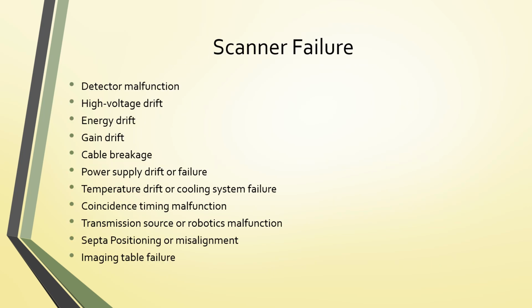There are a lot of things that can cause a scanner to fail. Malfunctions with the detector or detector block, high voltage drifting, energy drift, gain drift, cable breakage, power supply drift or failure, temperature drift or cooling system failure, coincidence timing malfunction, transmission source or robotics malfunction, septal positioning and misalignment, or imaging table failure. It is very common, especially with a little bit older PET-CT cameras that have the robotic arm for the QC source. It is very common for those robotic arms to malfunction.